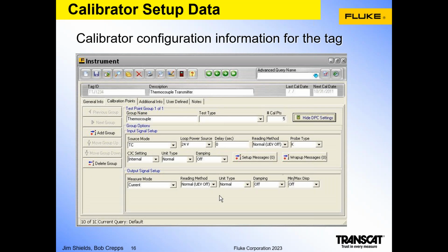Here's additional information. This discusses the configuration of the calibrator. For example, the source of the calibrator is going to be a thermocouple. We're going to turn on 24-volt loop power to power the instrument. We're going to measure current, et cetera. So with all this information, we should be able to download a tag to the documenting calibrator.